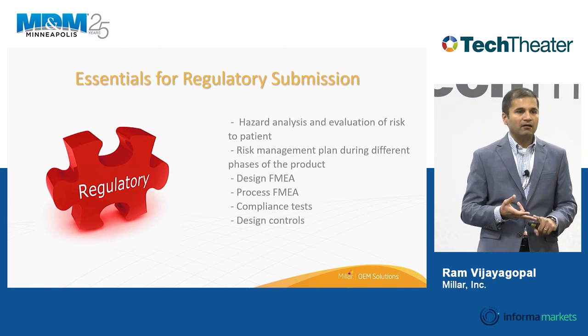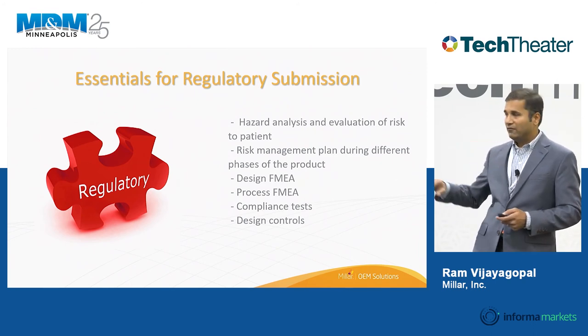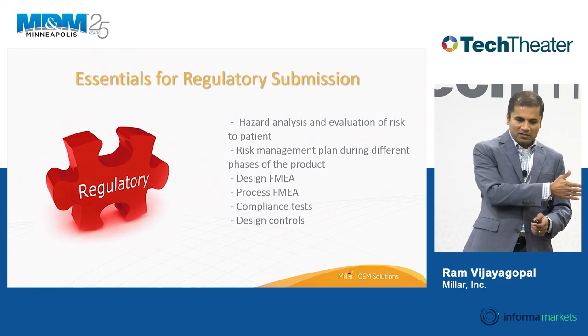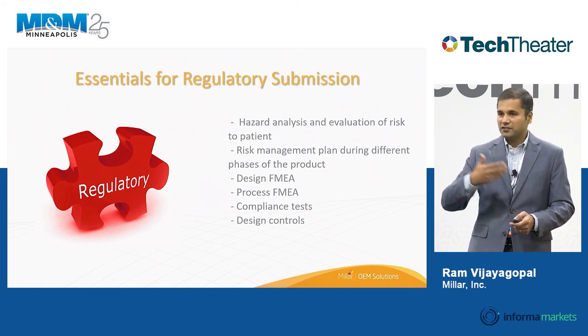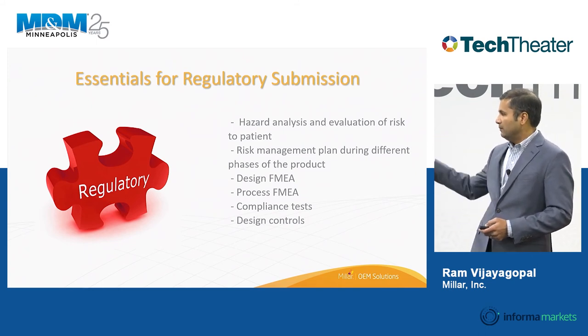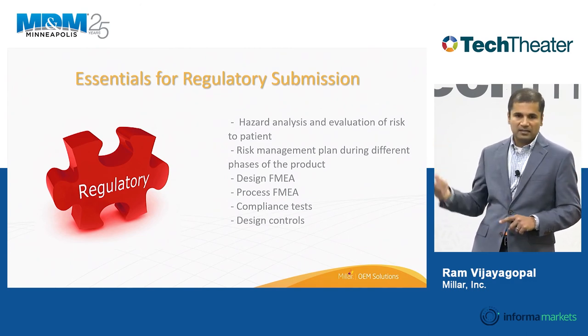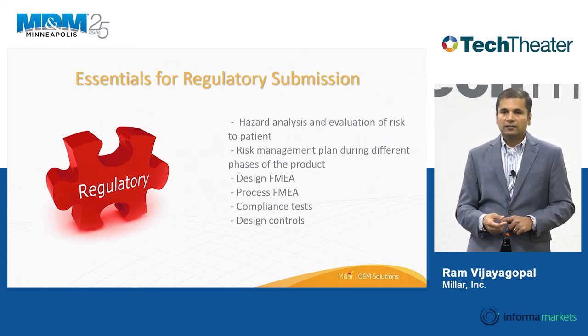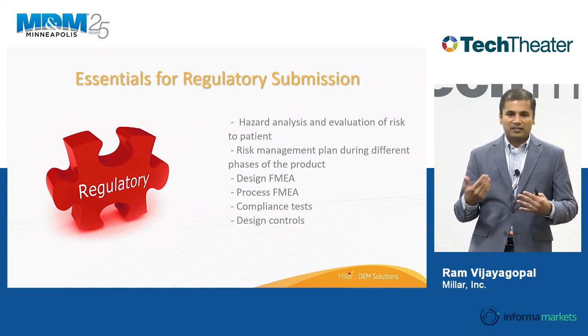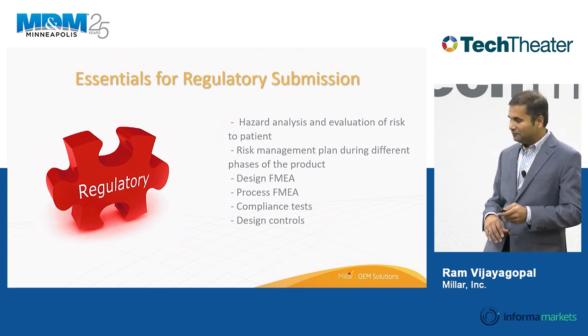Regulatory bodies like the FDA or under MDR want the same things: demonstration that you've identified all hazards, have a plan to mitigate them, and have a risk management plan spanning from design through manufacturing and even post-launch — with ongoing monitoring and adequate responses at each phase. Components of that plan include a design FMEA during the design phase, a process FMEA, compliance tests, and design controls to prevent uncontrolled changes as you progress through development.